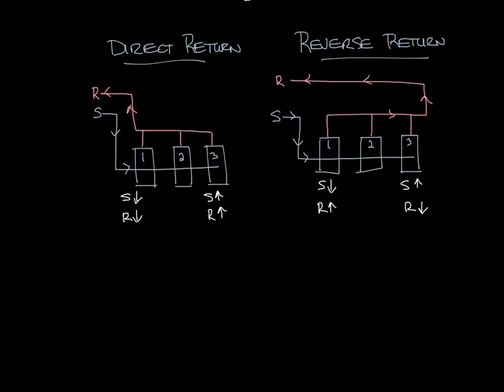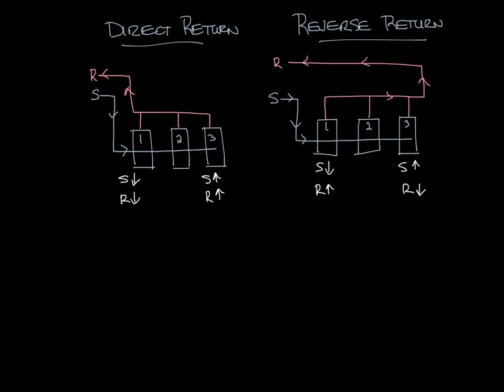Let me move this up just a little bit. Okay so with reverse return it's an inherently balanced system. All three units have essentially the same flow regardless of flow conditions. So you have more even flow through all the units.